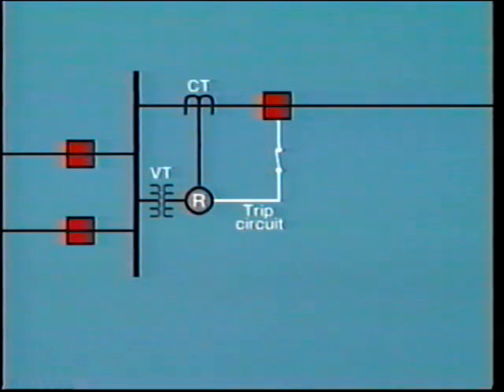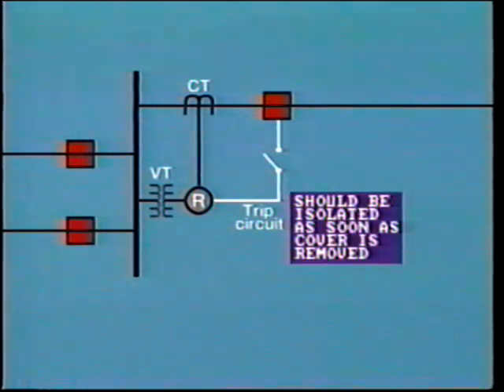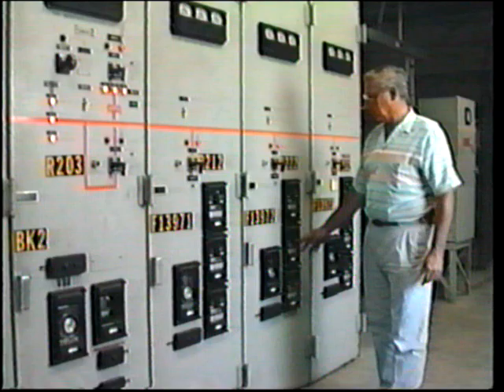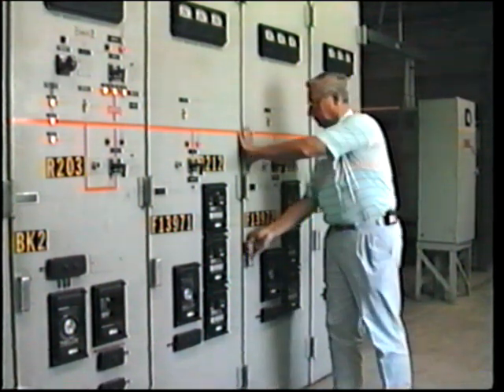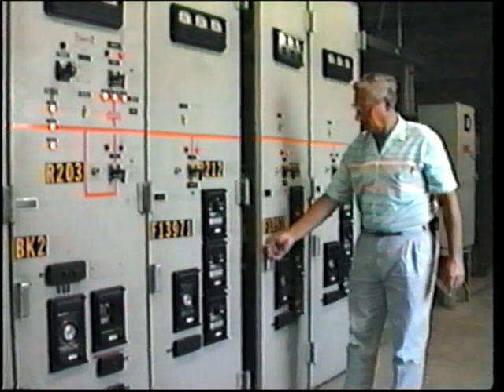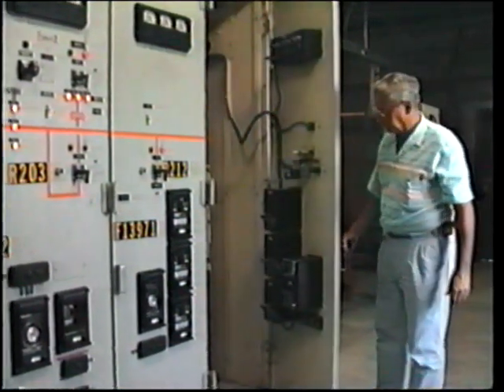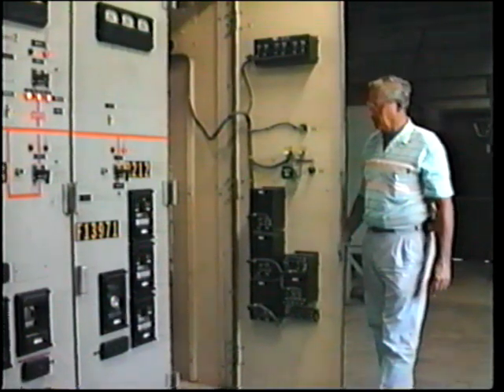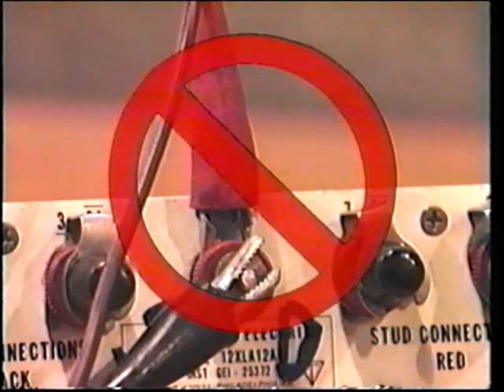So what have we learned from all this? Well, clearly there are several common conclusions resulting from these inadvertent trip incidents which occurred during in-service testing. One of these we have just looked at. That is the absolute necessity to isolate the trip circuits from the relay being tested. This should be done as soon as the relay cover is removed or before, if this is possible. Another problem is due to physical movement around this highly delicate equipment. Opening swing panels and removal of relay covers always requires care and attention. Make sure that you have the right tools. Alligator clips are a no-no on live current circuits.